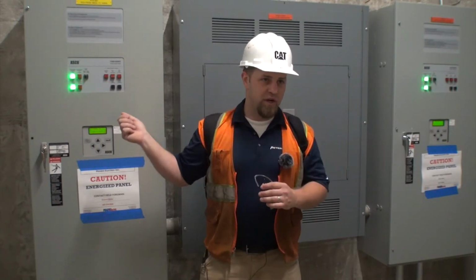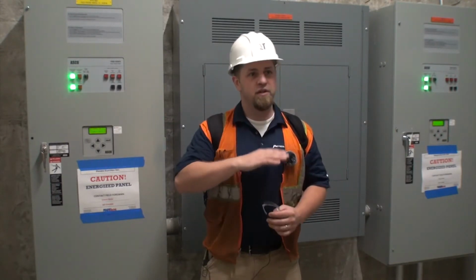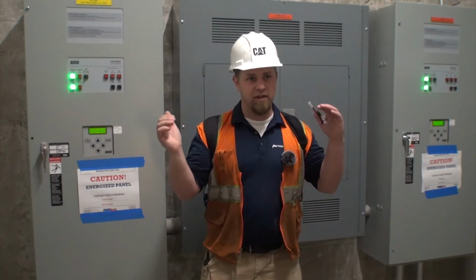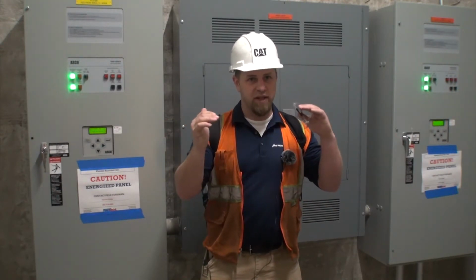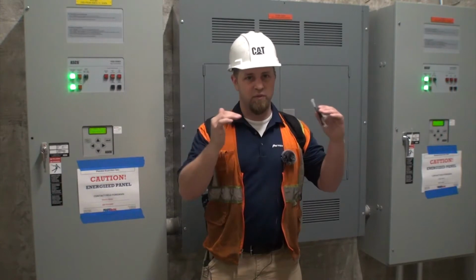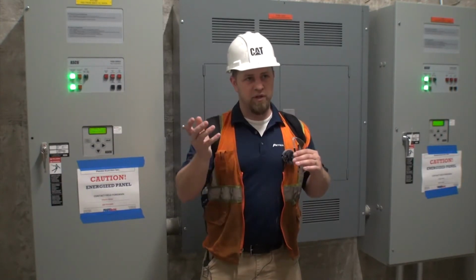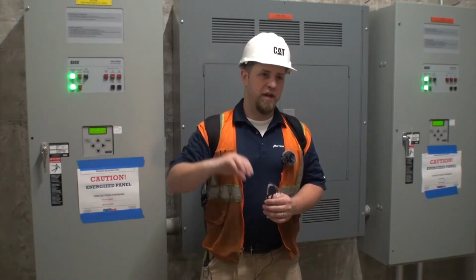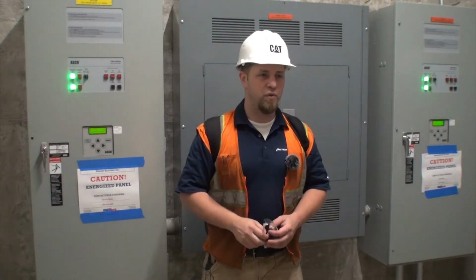So you go do this transfer, it starts, runs 30 minutes, but it doesn't like that it's not the same hertz. It's going to keep sitting there until it gets right where it wants to be. Then it will transfer off of load, then go to the 5-minute cooldown.